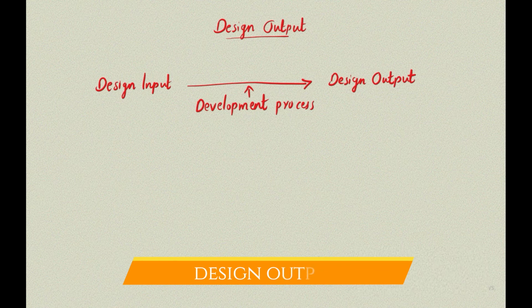So the company that is manufacturing the product should establish and maintain a procedure for defining and documenting design output that should allow an adequate evaluation based on the design input requirements. So the design outputs are to be controlled by defining acceptance criteria to ensure that proper qualification and function of the device is done. So also as a part of the design control process, the output shall be documented, reviewed and approved before it is released in the system.